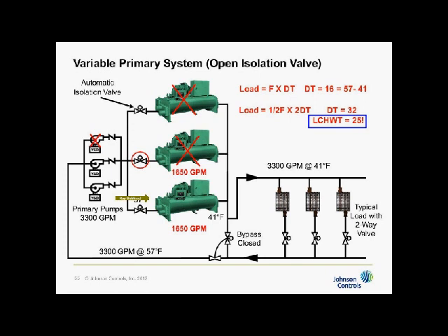It wants to get to 50, so it starts closing the vanes, but it takes a minute and a half for those vanes to get to the 50% load position, which is roughly 30% vane position. So it can't keep up with the 15 seconds that it took to open this valve. So this chiller that's almost fully loaded sees, up here in our formula where load is equal to flow times delta T, half the flow all of a sudden. So the only way it can do almost full load at that condition is to double the delta T. So my 57-degree return temperature is driven down to 25 degrees here.